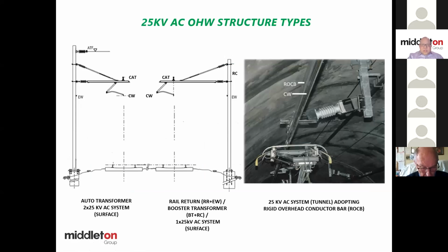Just to give you an appreciation of what each system would look like. So a rail return system would have the contact wire, catenary wires, and using the running rails as return. As an improvement, some systems install an earth wire, which is also bonded to the running rails, so that some of the return current will flow in the earth wire, cancelling the magnetic field of the contact wire and the catenary. I think I got my contact wire in the wrong place there.